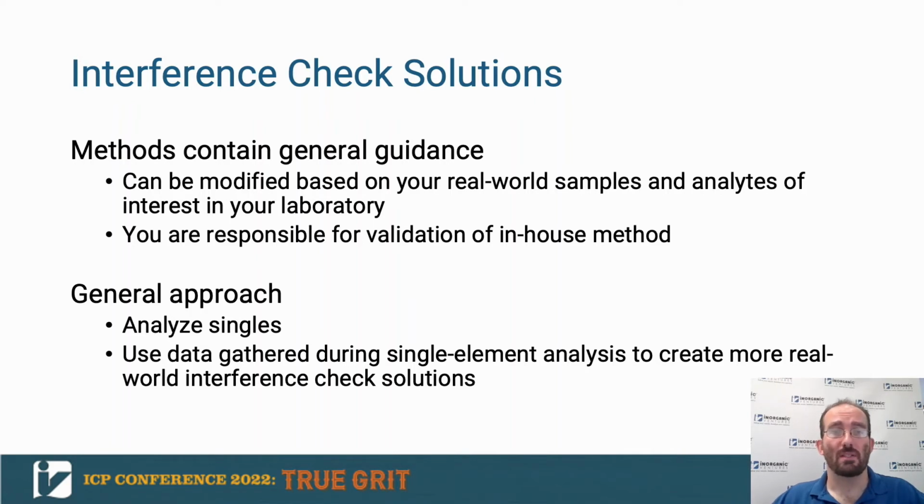For all of the methods we've discussed, you as an end user are responsible for all validation of any in-house methods you design. When validating your method, we recommend analyzing single element standards for every element you reasonably expect to be present in your samples. Once you have reviewed the spectra and characterized potential interferences, you can start to mix the elements together to more closely mimic your personal real-world samples.